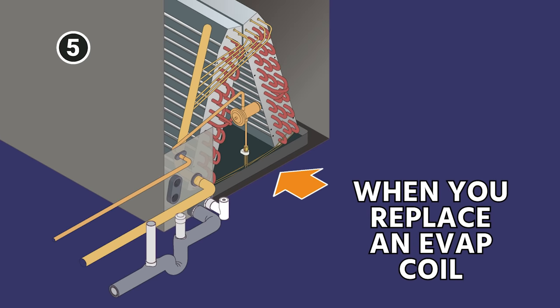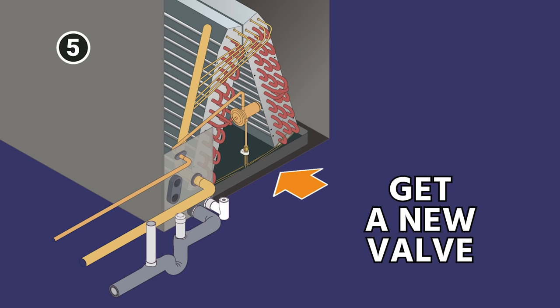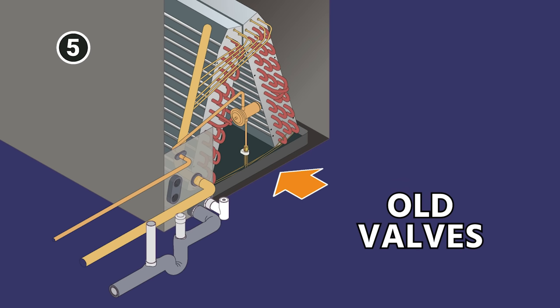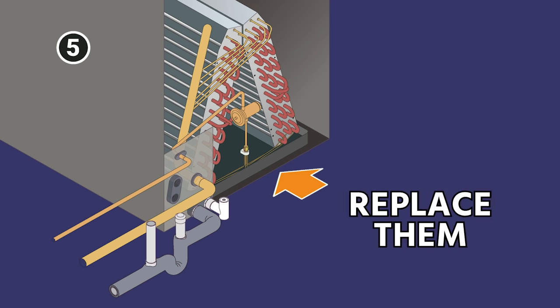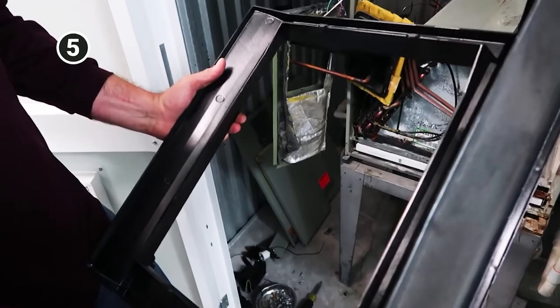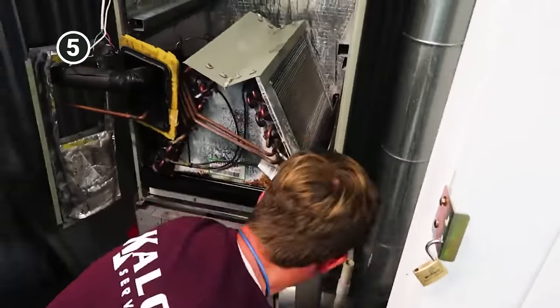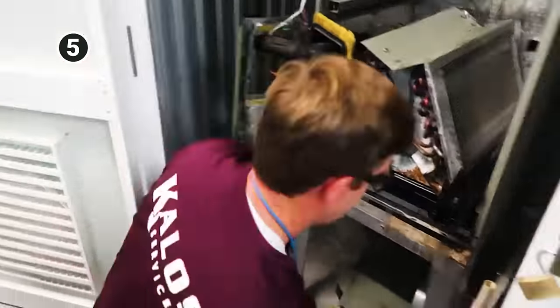I always suggest when you're going to replace an evaporator coil, just go ahead and get a new valve. If it doesn't come with one, it just makes good sense. Handling an old valve and trying to reinstall it, you're often going to break it, so it just makes good sense to go ahead and replace that. If you can replace a new drain pan, that also makes a lot of sense. Some of the most common issues that we see is folks forgetting to get a new drain pan and valve, and then when they try to reinstall them, those break.